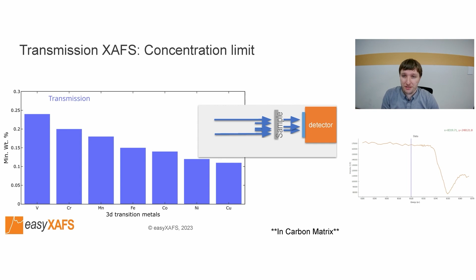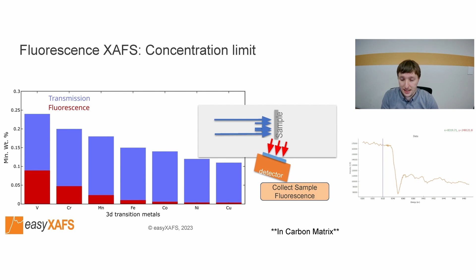When we bring this technique into easyXAFS spectrometers, we found that we could measure and achieve sensitivity all the way to sub 0.1 weight percent for 3d transition compounds, and even lower for certain elements. As an example of this fluorescence mode performance, we have Zane's measurements on a few 100 nanometer thin film of nickel oxide versus a nickel oxide pellet that we measured in transmission mode.